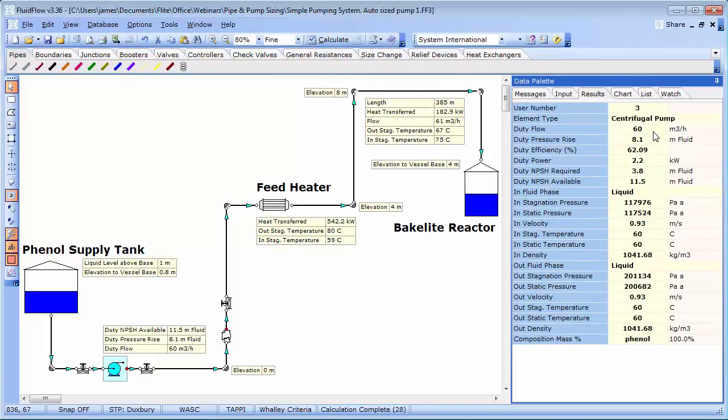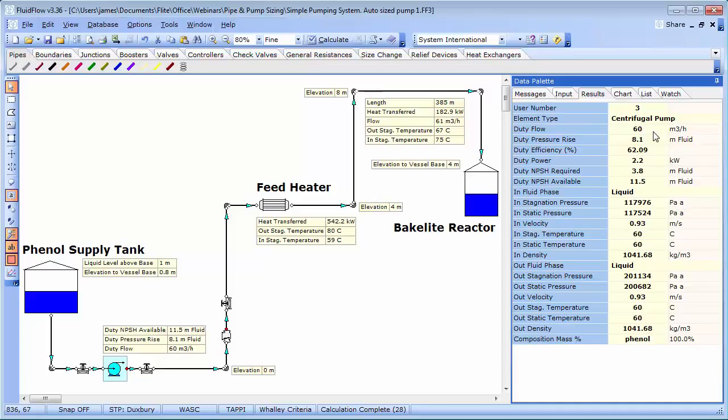If we increase the pump speed to 1,871 rpm, the duty flow now becomes 60 m3 per hour, with a subtle increase in duty pressure rise to 8.1 m of fluid. The duty efficiency is 62%, and the duty power is 2.2 kW.